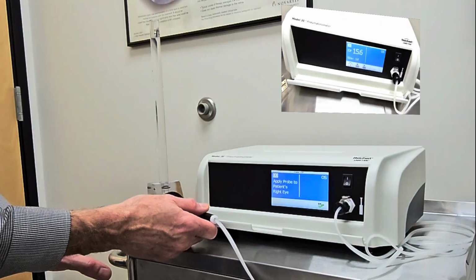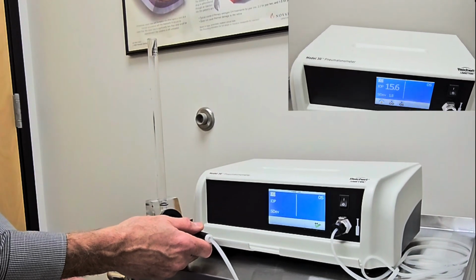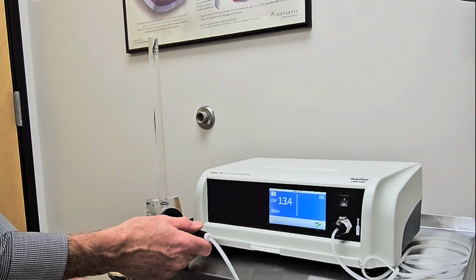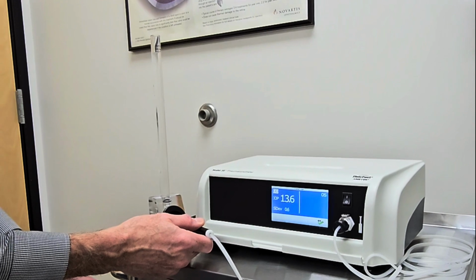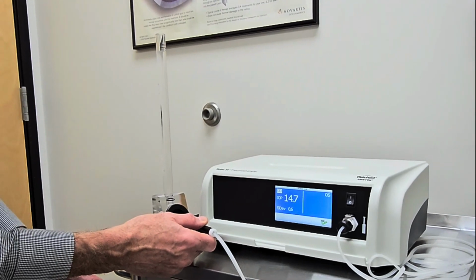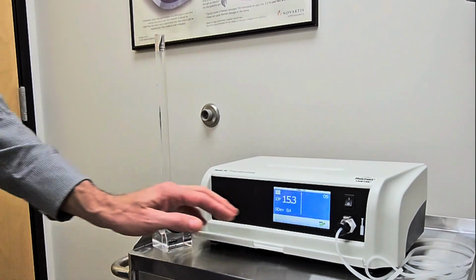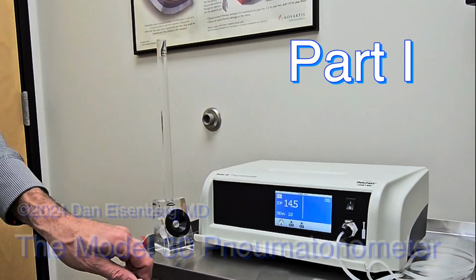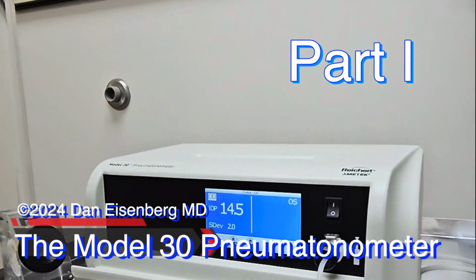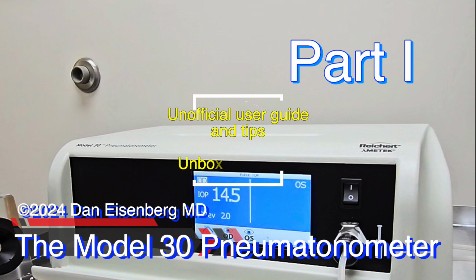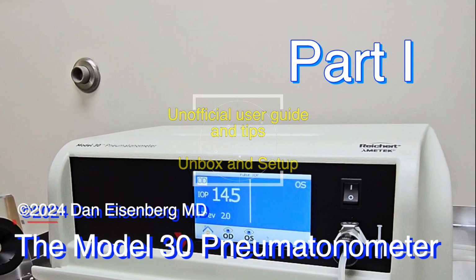And this reading should be within 15 millimeters plus or minus 2. So 15.6 is perfectly good. And then I like to do a second calibration anytime I have a brand new machine, brand new probe. And same thing, there we go, 14.5. So we're all good. This machine is up and running and ready for use. Stay tuned to part 2 for how to use the Model 30 Pneumatonometer.